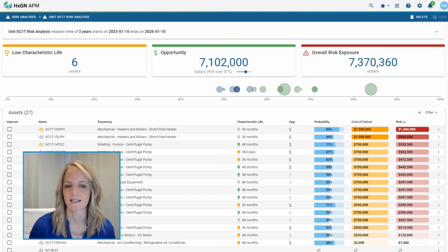So using this risk assessment, we are looking at existing operational risk relative to industry standards, and then monetizing the consequence of that risk exposure. The analyzer evaluates historical performance of the assets, calculates a mean time between failure, which is based on EAM data about when corrective and reactive work was done, and compares that to industry benchmarks so that you know where to focus first and ultimately get the biggest bang for your buck.